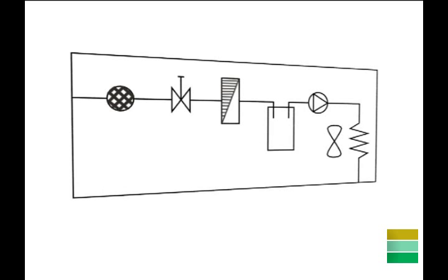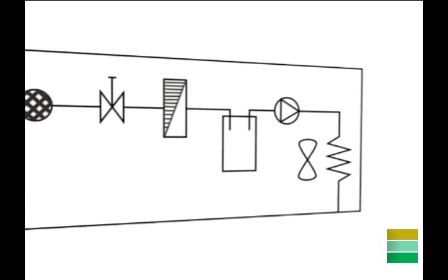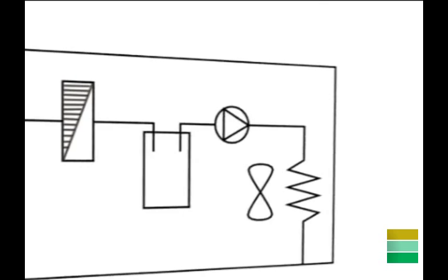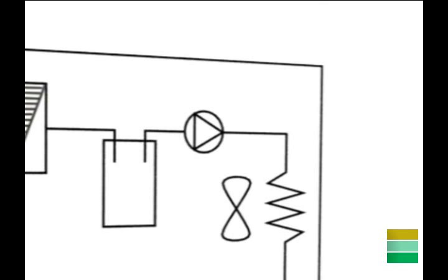The refrigerant in vapor phase is taken by the compressor of the main machine, it condenses and returns to the bottle in a cooled liquid phase. This will cause a pressure differential for the new cycle of cleaning greater than in the first injection.